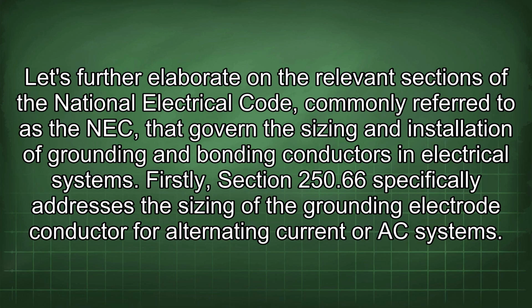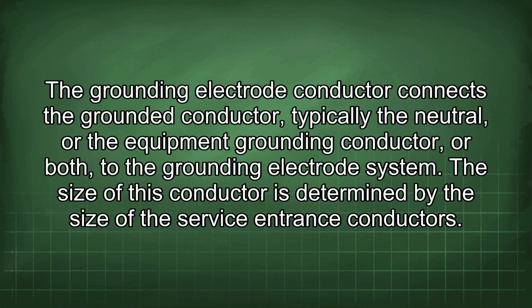Let's further elaborate on the relevant sections of the National Electrical Code, commonly referred to as the NEC, that govern the sizing and installation of grounding and bonding conductors in electrical systems. Firstly, section 250.66 specifically addresses the sizing of the grounding electrode conductor for alternating current or AC systems. The grounding electrode conductor connects the grounded conductor, typically the neutral, or the equipment grounding conductor, or both, to the grounding electrode system. The size of this conductor is determined by the size of the service entrance conductors.